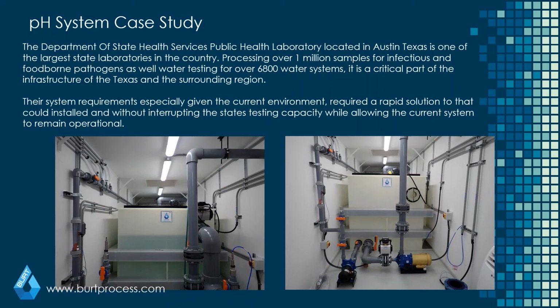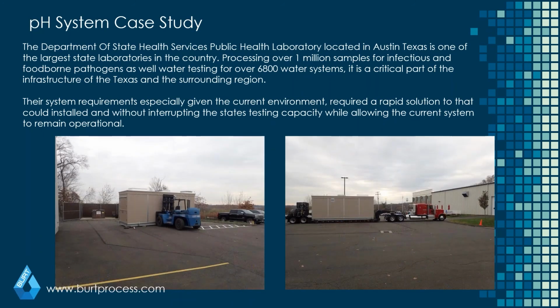But sometimes people do require it, depending on the state. And obviously, this being a government lab, there were some different requirements in this case, such as fire suppression systems, and some level of building permits still had to be pulled for this application. But that's how much bigger these systems get when you're talking about a pH-based system. You can see the outside of one of the containers here. In this case, due to room allotment, they ended up with two containers as opposed to one large one that could then be installed on site.